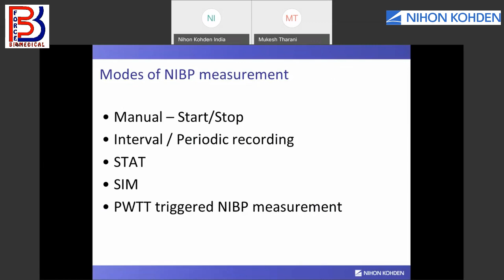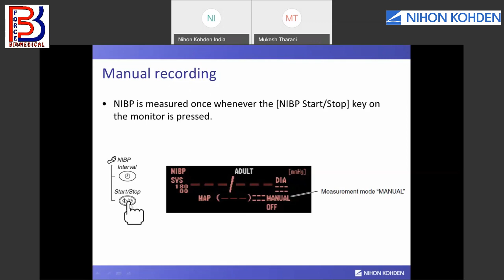In the manual recording, it's a very simple method. You just have to attach the cuff to the patient's arm and press the start button. You can see on the patient monitor screen that the measurement mode is manual. By this the monitor will take the reading only once. Whenever they require the BP, the nursing staff or clinician in the ICU presses the start button. If the cuff is inflating and they don't want it, they can press the button again to stop it.